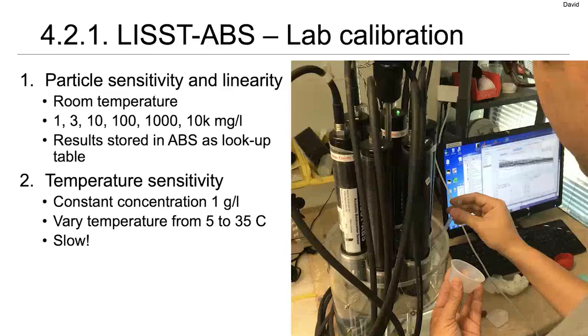10,000 milligrams per liter. The electronic response of the ABS is not perfectly linear. Like any ultrasound receiver, it's got some nonlinearities inherent in the circuitry. But we correct for all that by simply making a lookup table with these 6 reference concentrations, and interpolating between the measured concentrations. And that's enough to give us quite good conformity with the response, an effective linear response.